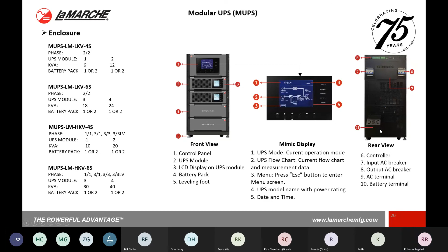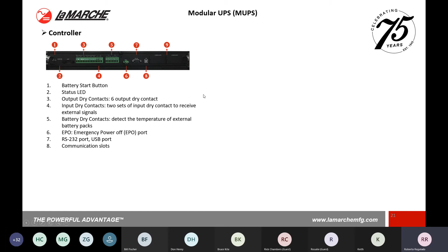Now moving on to our controller - you saw a little bit of that snippet in the previous slide. You can see different accommodations for your output and input contacts; you can go through the manual for more detail on how to set that up and what signals you can receive. You also have battery contacts to detect temperature of external battery packs, an EPO port for EPO functionality if required on the rest of your system, RS-232 and USB ports, and we also have an SNMP connection as well, which you'll see in this part too.